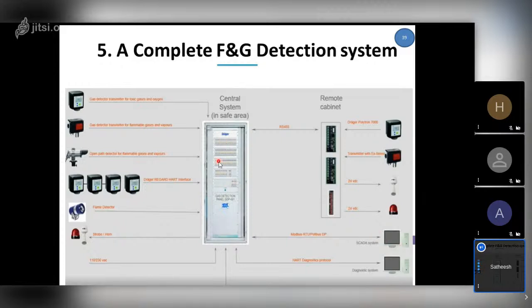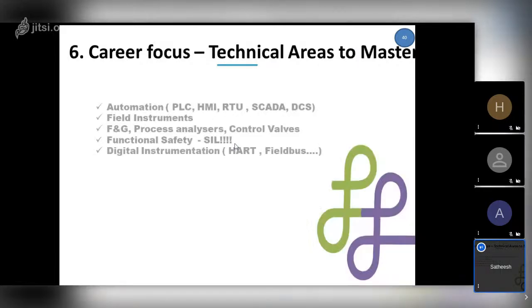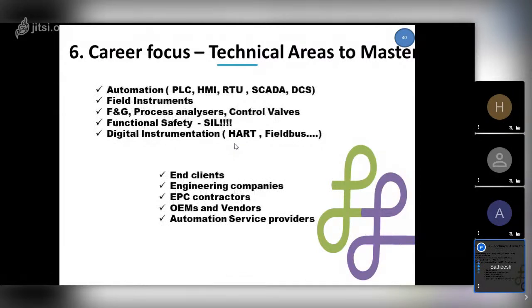Otherwise, here we only see kinds of indicators. Here we can have nice graphics to show which area has a gas leak. All those things are possible, like a third-party system. And another one, like health diagnostics, meaning the equipment also has quite intelligent diagnostic information, and that will be kept in another system. We call it the asset management system. All the diagnostics, when this equipment needs maintenance, when we need to replace the sensor, when we need to calibrate, the whole thing will be stored here to ensure the scheduling is done for preventive maintenance. Okay, this is my final slide, and I will stop here.